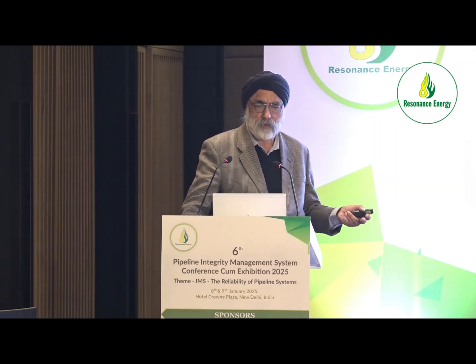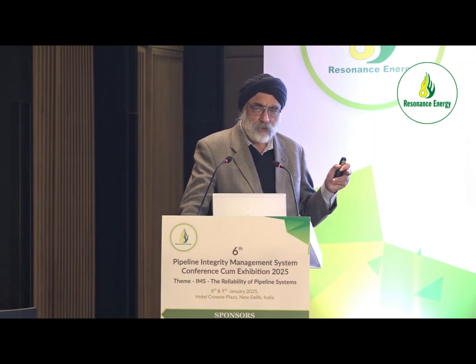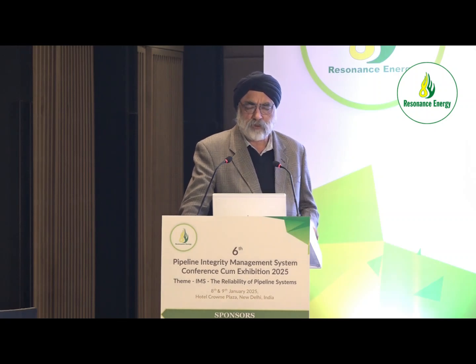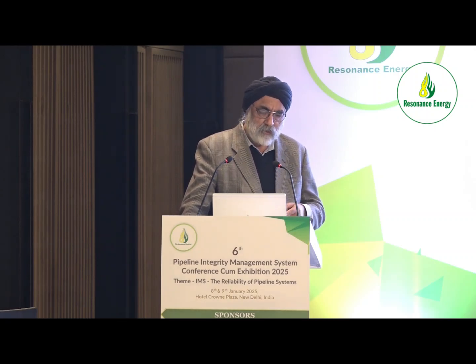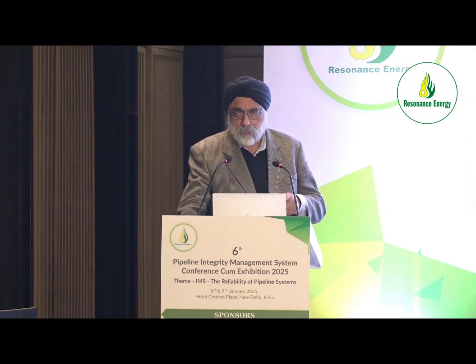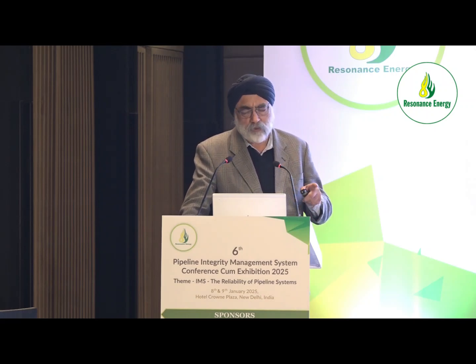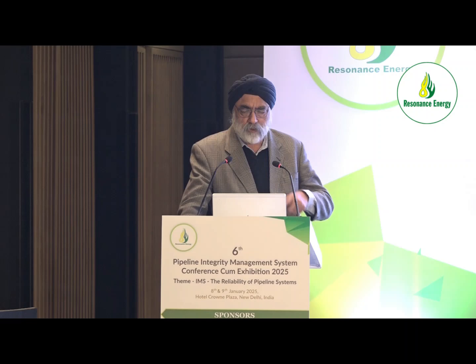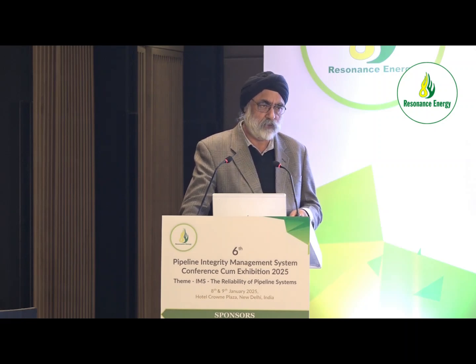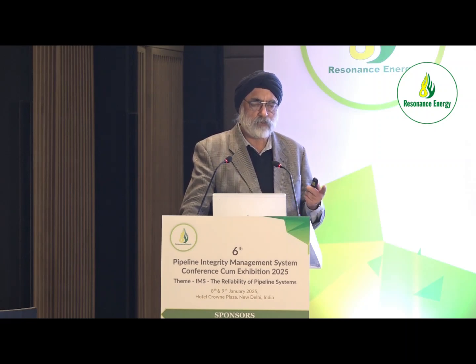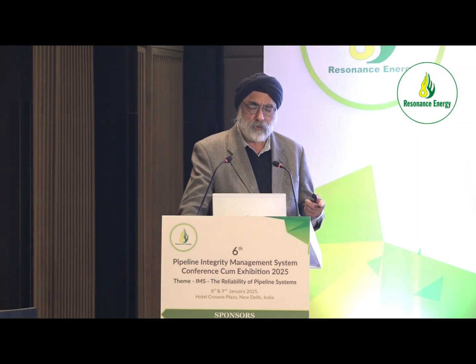They'll have pigging stations about every 130 or 140 kilometers, and SV stations about every 30-35 kilometers, with maybe one or two branch-offs. The problem with the CGD network is that we have SVs which are either directly buried or mostly in buried RCC pits every 3 kilometers. That changes the whole scenario of how we operate and maintain our CP systems.